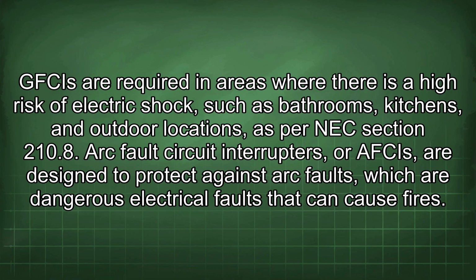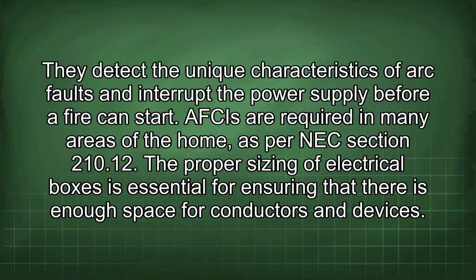Arc fault circuit interrupters, or AFCIs, are designed to protect against arc faults, which are dangerous electrical faults that can cause fires. They detect the unique characteristics of arc faults and interrupt the power supply before a fire can start. AFCIs are required in many areas of the home, as per NEC section 210.12.